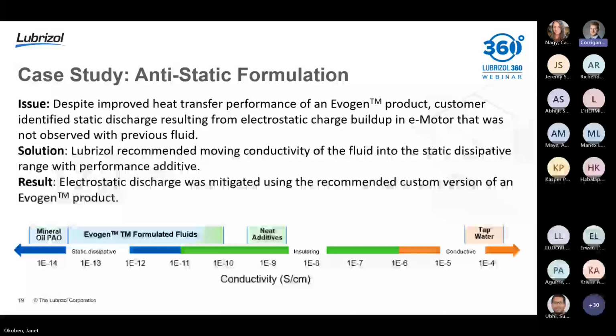Starting on the far left, you have things that are extremely insulating, like pure mineral oils or synthetic PAOs. On the far right, you have a conductive fluid, something like tap water with dissolved electrolytes. What we found was that if your fluid is too insulating, it can lead to static buildup. It was prevalent and noticeable because they were getting arcing of that static buildup across their connectors, and we saw pitting of the material.